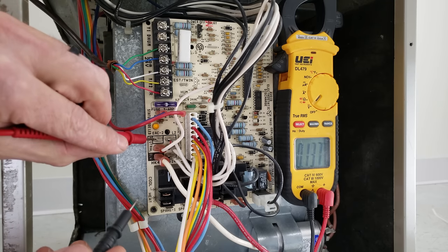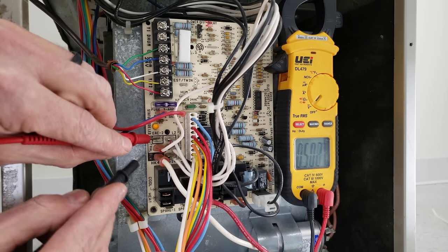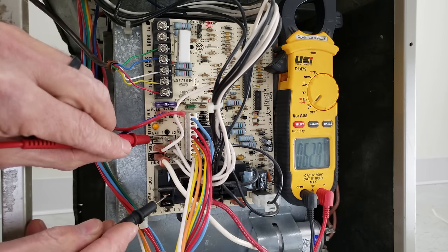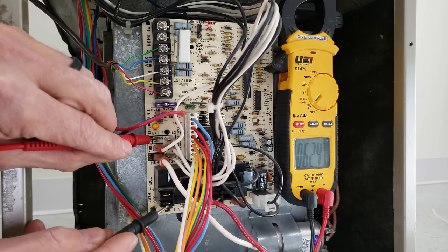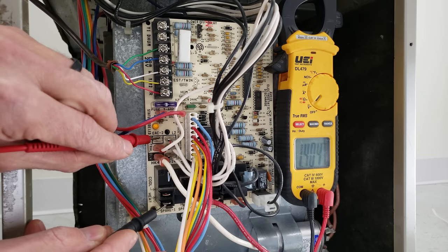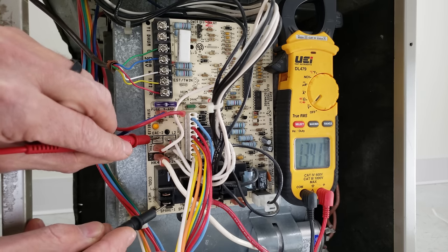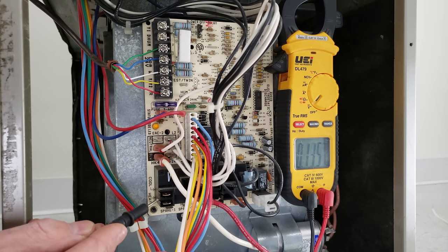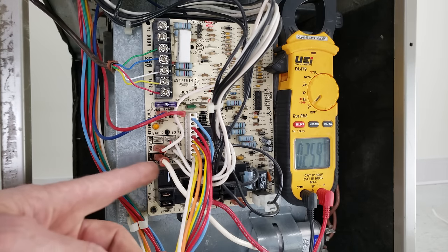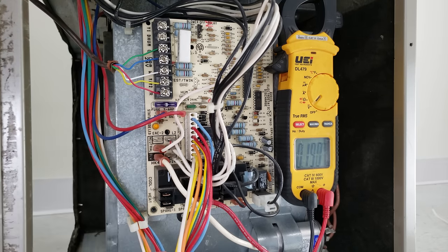In this case, you can see when we measure over on the common and to our cooling tap, we have 0 volts. And from our common to our heat tap, we have, once again, 0 volts. So that's what it should have. So in this case, this black box and the relay contacts are good.